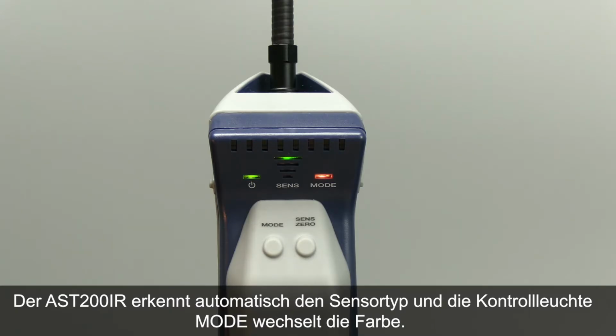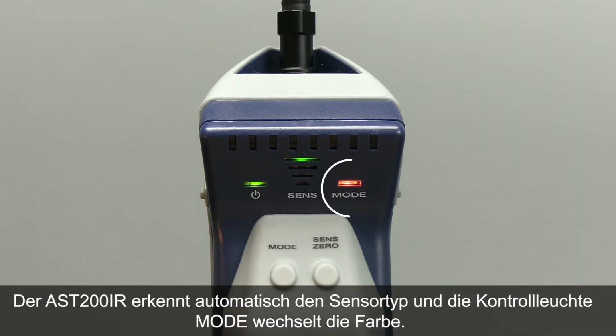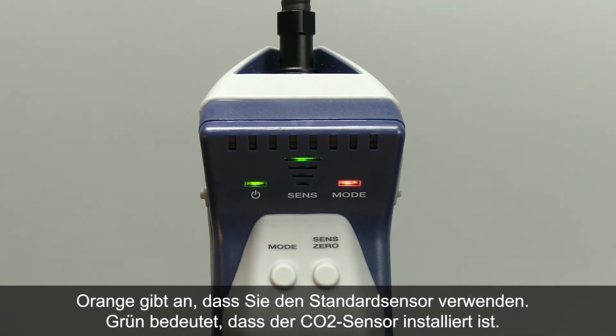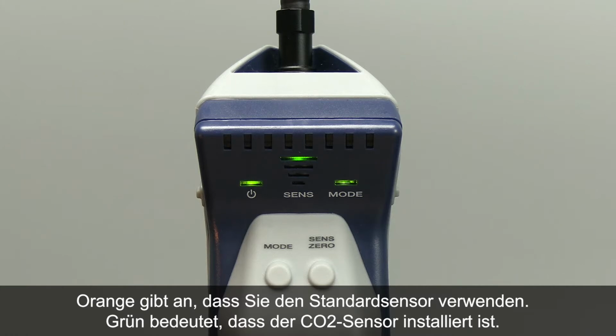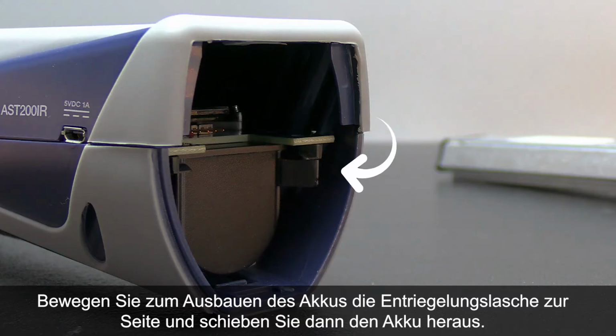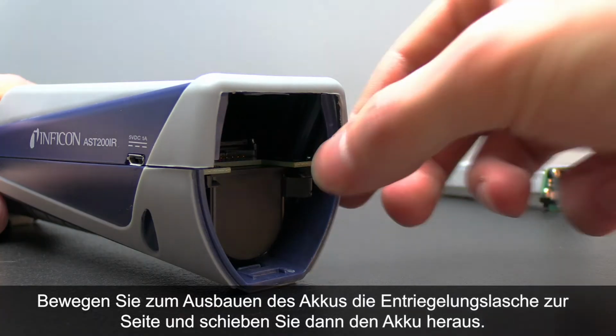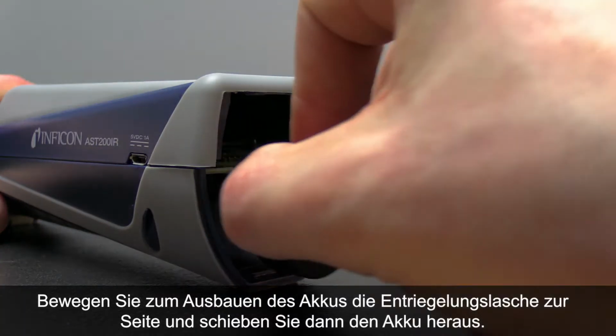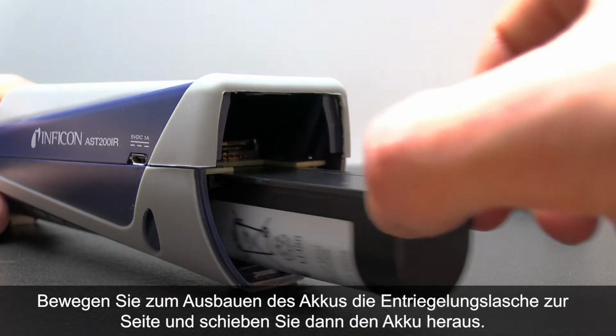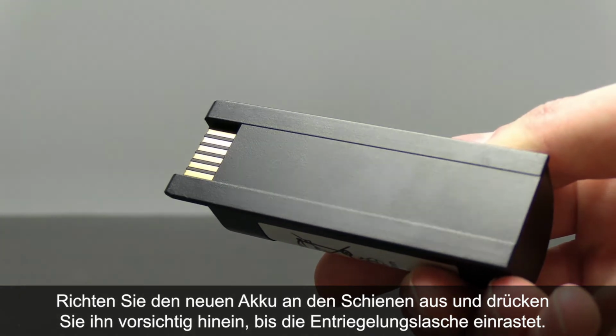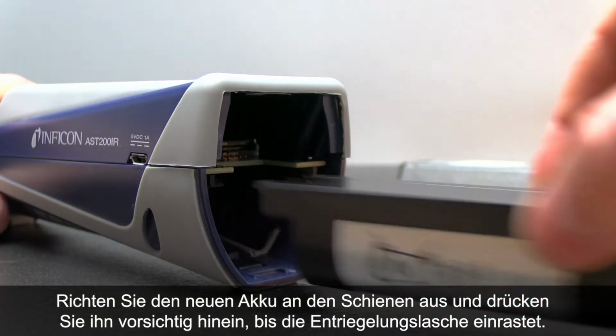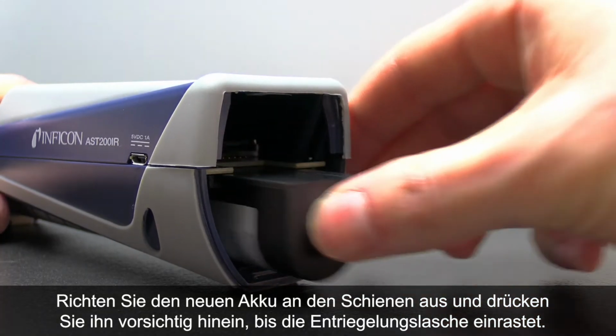AST200IR will automatically sense the sensor type, and the mode indicator will change color. Orange indicates that you're using the standard sensor, and green indicates the CO2 sensor is installed. To remove the battery, move the release tab to the side and slide the battery out. Align the new battery with the rails and gently push in the battery until the release tab engages.